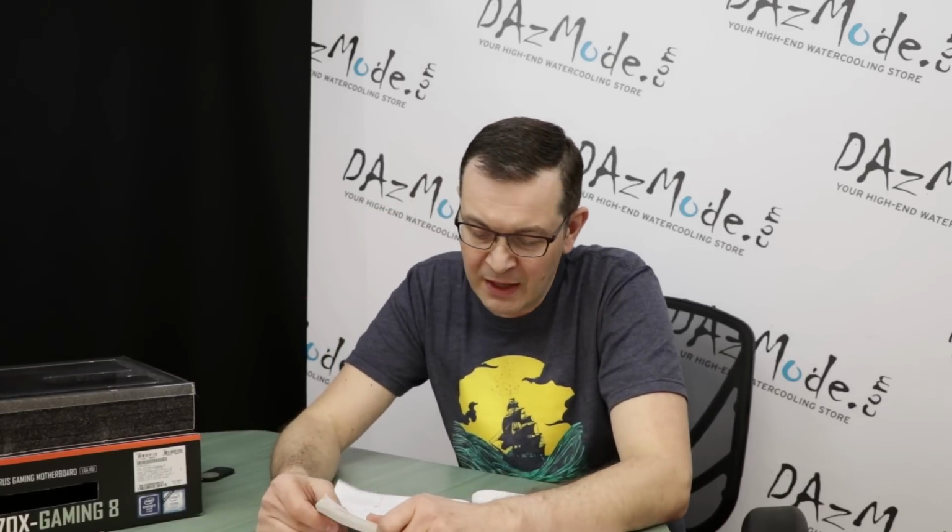You might want two, but the reason isn't performance. You might want some redundancy, because any electrical device can still fail. And if you don't have protection that shuts your system down when the temperature goes up, then if one pump is gone, the second still goes. For that reason, I always use two. But it's more a question of being paranoid than really necessary. Okay? All right.